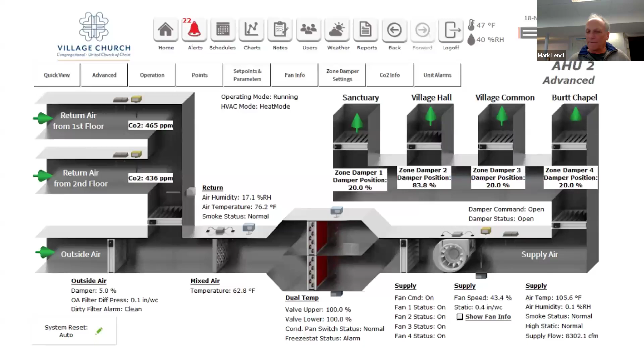Then it goes through 4 fans and it goes out to our 4 zones, each of which have dampers. And what it's showing here is these 3 zones to our Sanctuary, Village Common, and Burtt Chapel are in their minimum position of 20% airflow, because you always need to have some air exchange there, but minimal heating. And then Village Hall, where we had activities going on, is up at 83% because it needs more heat to supplement the radiators. That kind of shows you how a rooftop air handling unit operates.